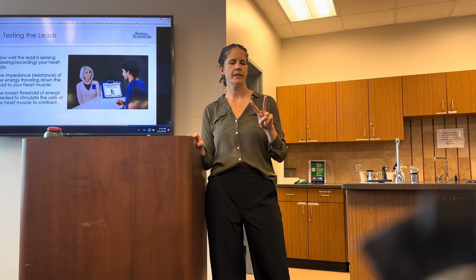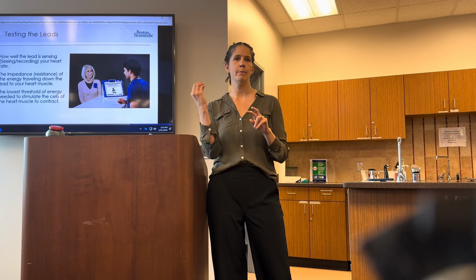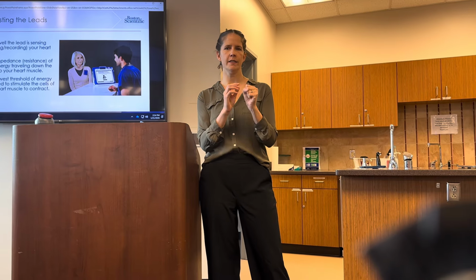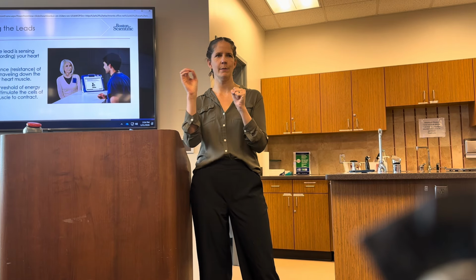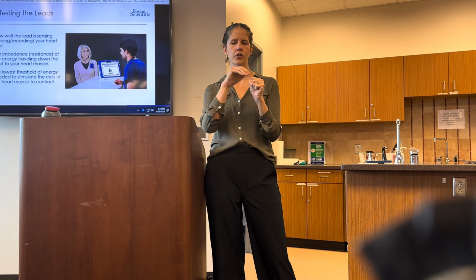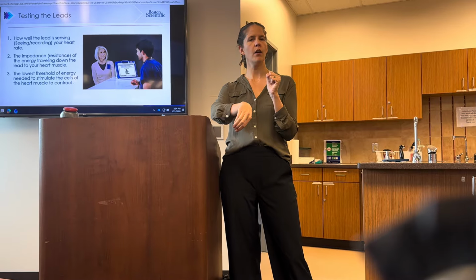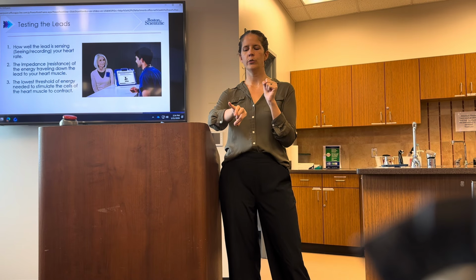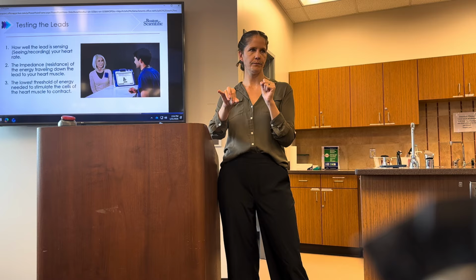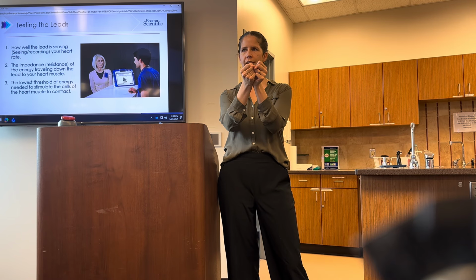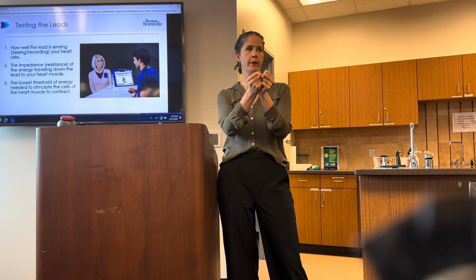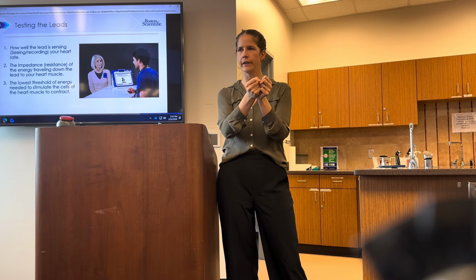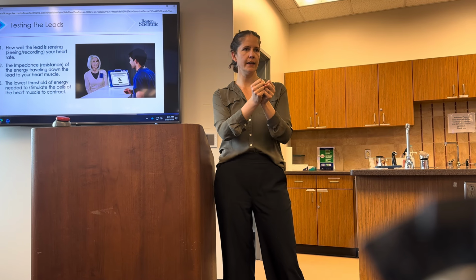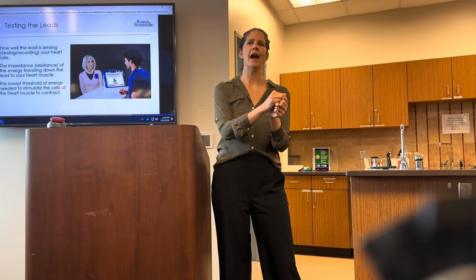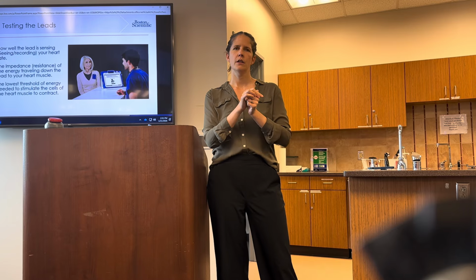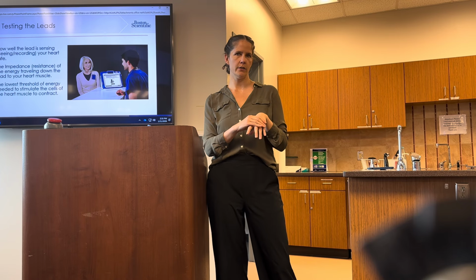Second one is we're sending energy down a line, which will have impedance. So that's just the resistance. How hard is it for the pacemaker, the defibrillator, to send that energy down to your heart to be able to stimulate your heart cells. There's a kink in a hose, right? So it's really hard for any water to get out of that hose. That would be an issue. So same thing, if there's a big kink in your lead, we'll see a much higher number, we're like something's wrong. So we use that to tell your lead's looking okay.